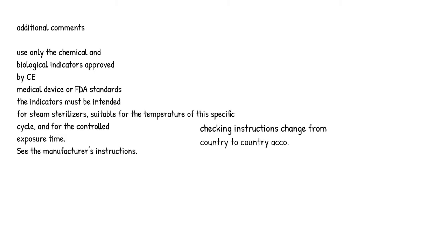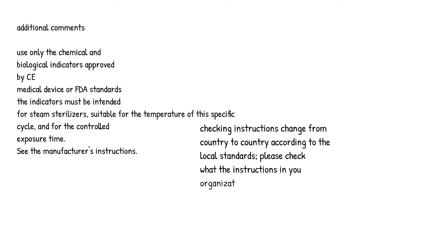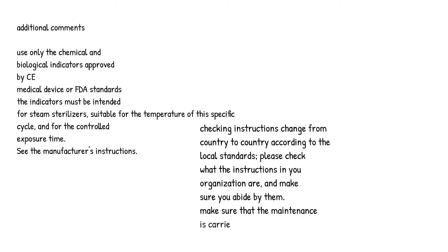Additional comments. Use only chemical and biological indicators approved by CE medical device or FDA standards. The indicators must be intended for steam sterilizers, suitable for the temperature of this specific cycle, and for the controlled exposure time. See the manufacturer's instructions. Checking instructions change from country to country according to local standards. Please check what the instructions in your organization are, and make sure you abide by them. Make sure that maintenance is carried out according to the instructions in the Operation and Maintenance Manual.